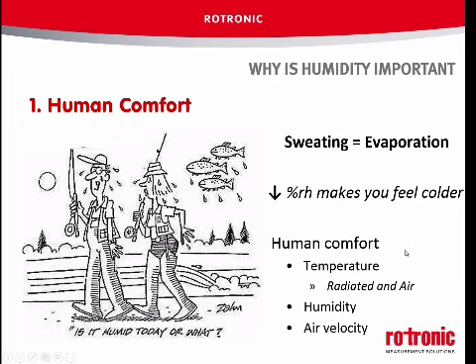Just as a bit of background, the 4 key areas that affect human comfort are temperature, which is a combination of the radiated and the actual air temperature. Radiated is important as we replace traditional lighting with LED lighting, clearly reducing the radiated heat effect. And then of course humidity, as mentioned, but also air velocity is important. If we're blowing air fast over people, you will feel colder. That's why a fan, despite blowing the same temperature air over you, makes you feel a little bit colder because of that evaporation effect.